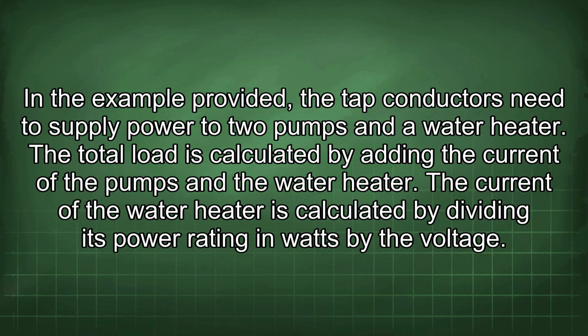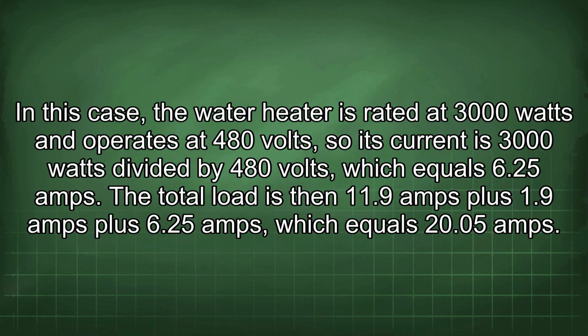In the example provided, the tap conductors need to supply power to 2 pumps and a water heater. The total load is calculated by adding the current of the pumps and the water heater. The current of the water heater is calculated by dividing its power rating in watts by the voltage. In this case, the water heater is rated at 3000 watts and operates at 480 volts, so its current is 3000 watts divided by 480 volts, which equals 6.25 amps.